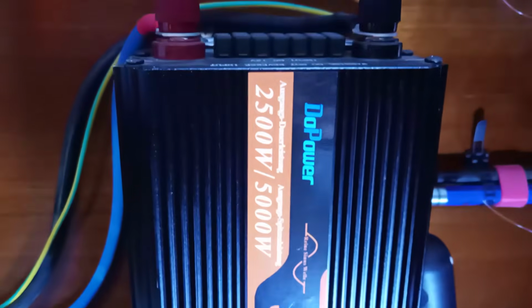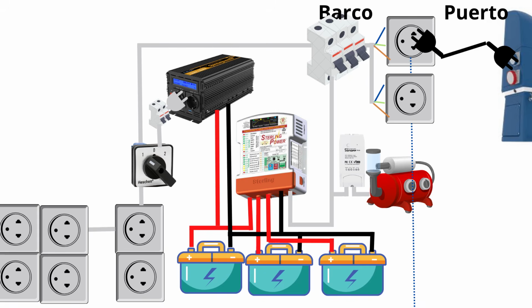Almost all inverters come with built-in overload protection systems, which will protect the installation without you necessarily needing separate circuit breakers, although considering the price they typically cost, it still doesn't hurt to install one anyway. The residual current device can be essential, and should be installed very close to the power source and connected to proper ground. I used a video to help reinforce my setup and add a residual current device on the inverter's direct output, so I can be confident everything is working properly and feel safe.